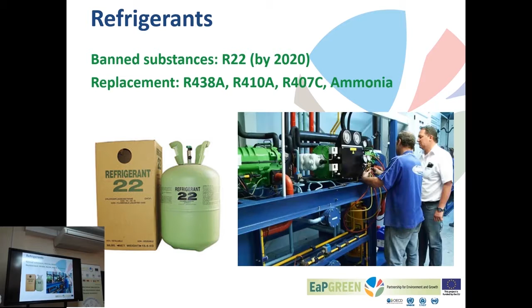Some practical hints for saving energy with refrigeration. Refrigeration becomes effective if I can increase the temperature of cold. So if in a cold storage I need 7 degrees, I should not go for 6 or 4 degrees, because every degree I allow less cold temperature comes at the cost of 4% of electricity. So as a rule of thumb, if this room was air conditioned, setting the set point to 18 degrees instead of 25 would cost 30% of electricity, more or less. So every degree I can increase the temperature of cold saves about 4% energy.